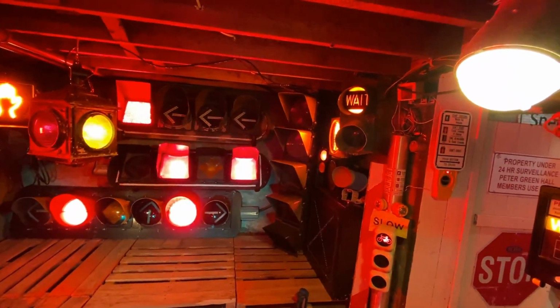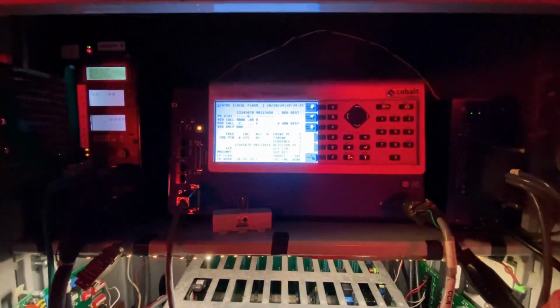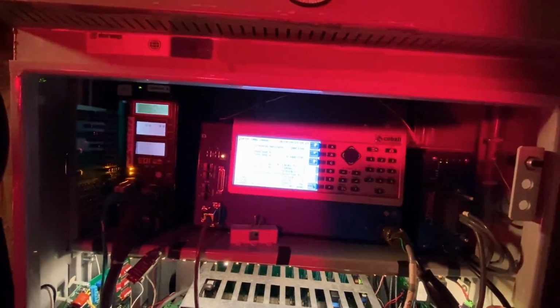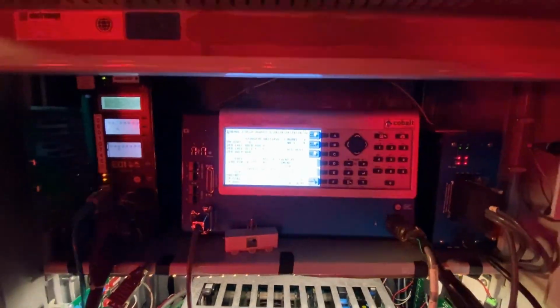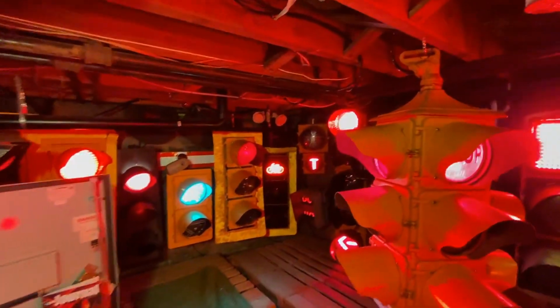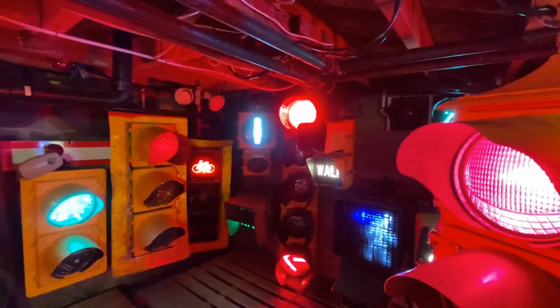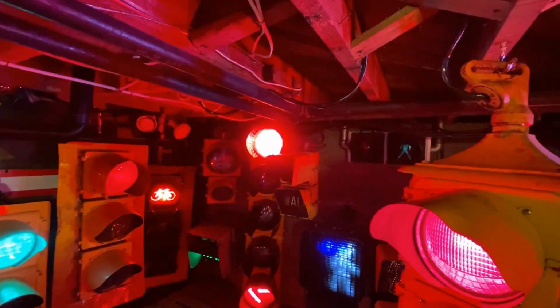Now we're back in this mode. Actually, I think I might have messed it up, so I'm going to put it into flash. Alright, now we're going to cycle the phases again. It didn't cycle them properly when I was messing with it. Now it's bringing up the exclusive pedestrian phase, as well as the transit.